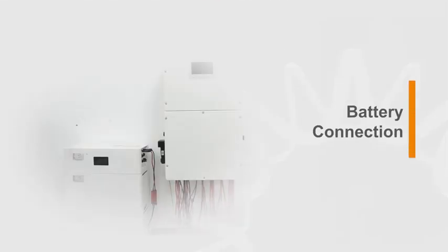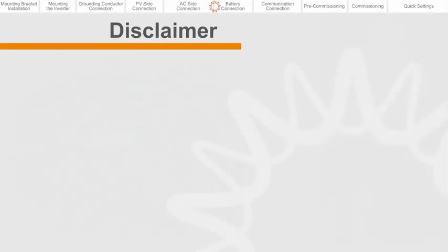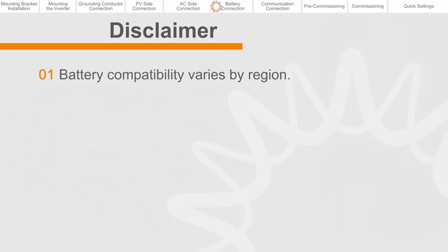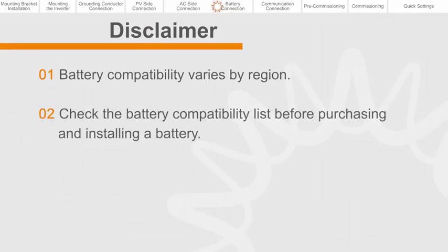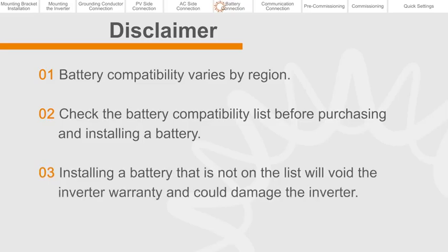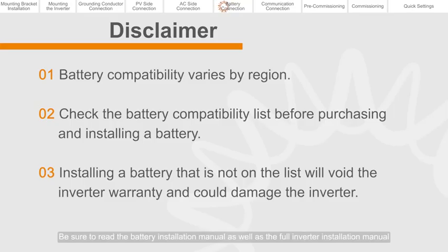Battery connection. Disclaimer: battery compatibility varies by region. Check the battery compatibility list before purchasing and installing a battery. Installing a battery that is not on the list will void the inverter warranty and could damage the inverter. Be sure to read the battery installation manual as well as the full inverter installation manual.